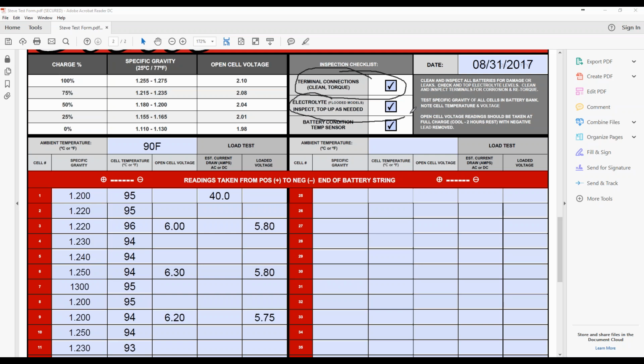Electrolyte: inspect, top up as needed, especially flooded models. If you've got a flooded battery, you spot check your specific gravities. You notice a half dozen or a dozen of the cells are a little bit low on electrolyte. You take some distilled water and put it in those batteries, top them up, do a full recharge, and then spot check your cells again afterwards. That's a good thing to do.